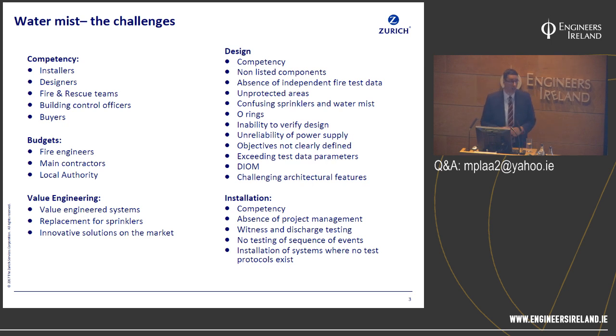And we're also finding water mist being installed in areas where there are simply no test protocols, and the installer has simply ignored the fact there is no test protocol to underpin and support that water mist installation. They've gone ahead and done it. My classic case is the hanging garment storage, 25 metres high. There is no way water mist would have ever worked in that environment. The fire consultant was going to go ahead with that if I hadn't just pulled his braces back a bit.